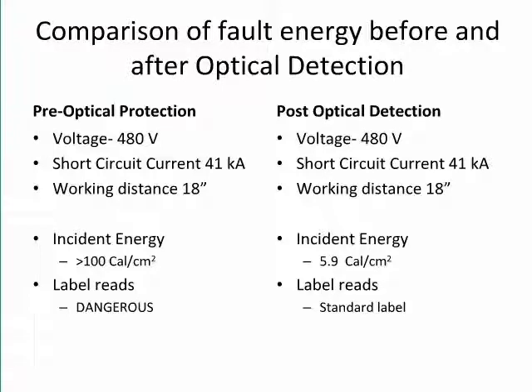Is the clothing available for this? Yes, it is. But the blast pressure is going to be so high that the person, even with the flash suit, will be thrown away. If you put in optical detection, with the same parameters of short circuit and working distance, you can see you have reduced it to about 5.9 calories per centimeter squared. That risk, after you do analysis, may be tolerable. But keep that in mind.